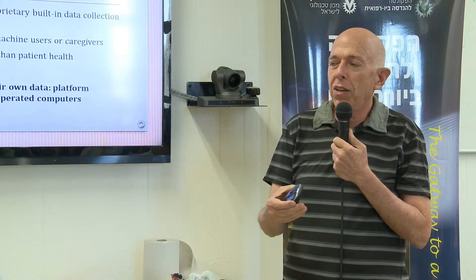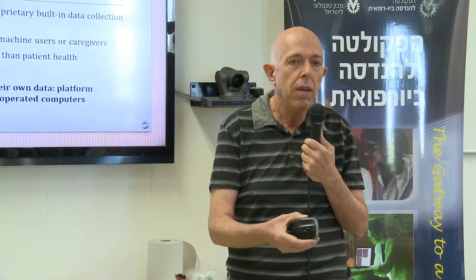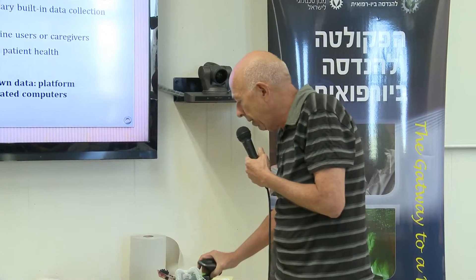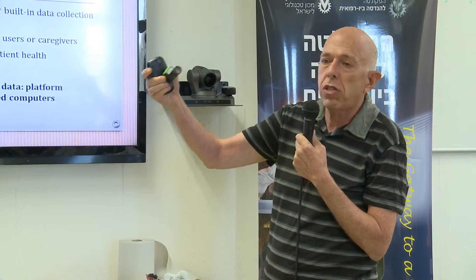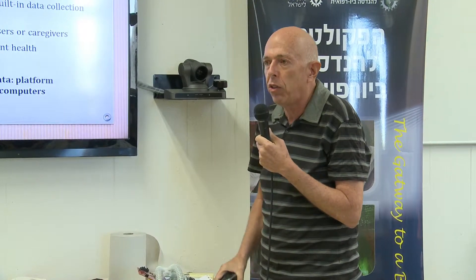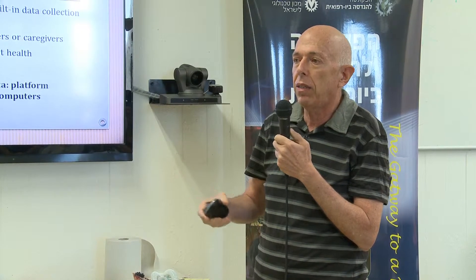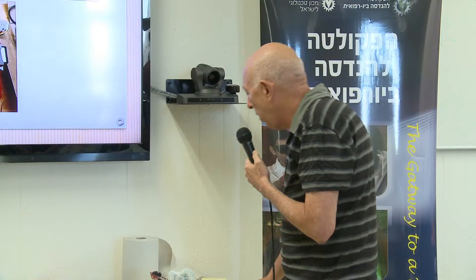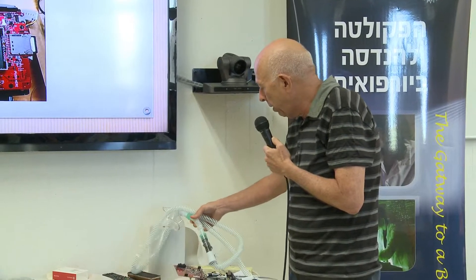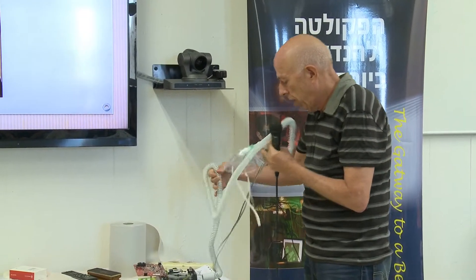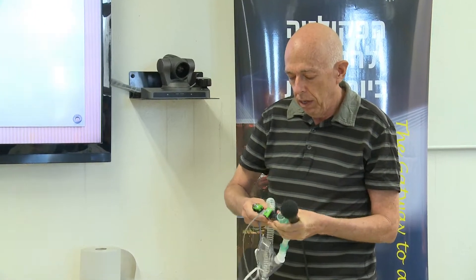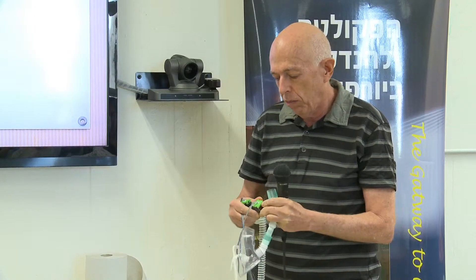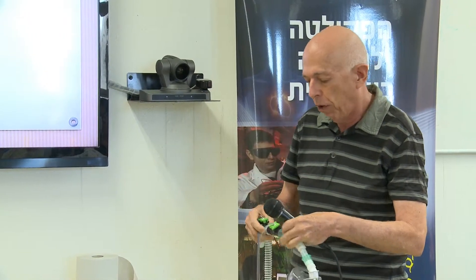The question came: how can we make generically all the devices available to patients today cloudified? Basically adding sensors or standard sensors like inline pressure sensors in a way that will be generic, not brand dependent, and able to collect the data and provide value to the patients. The idea is to connect inline sensors — taking the standard tubing and connecting the sensor module in between — so this is device independent, requiring only standard diameters and form factors.